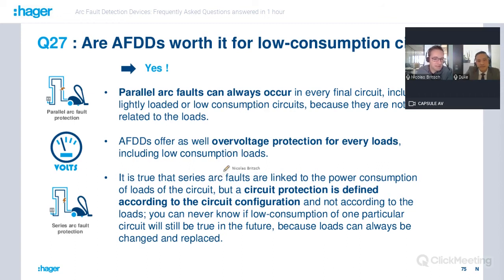So it is true that series arc faults are linked to the power consumption of loads of the circuit. But the circuit protection is defined according to the circuit configuration, because you can never know if low consumption of one particular circuit in a building will still be true in the future, because the loads can always be changed and replaced. That's why, of course, AFDDs are worth it for low consumption circuits. Okay, thank you.